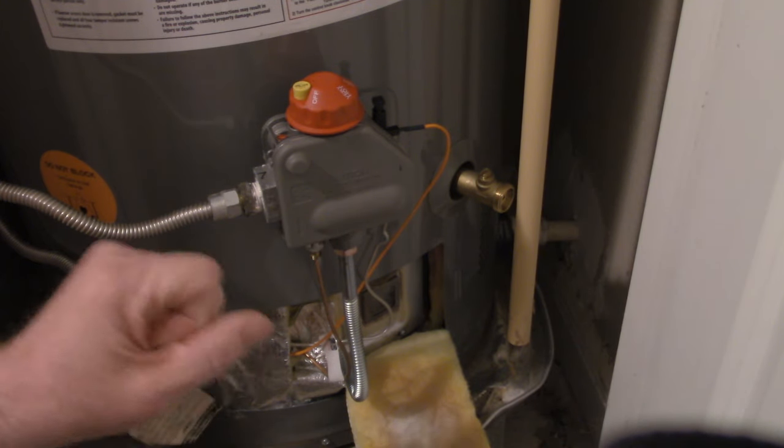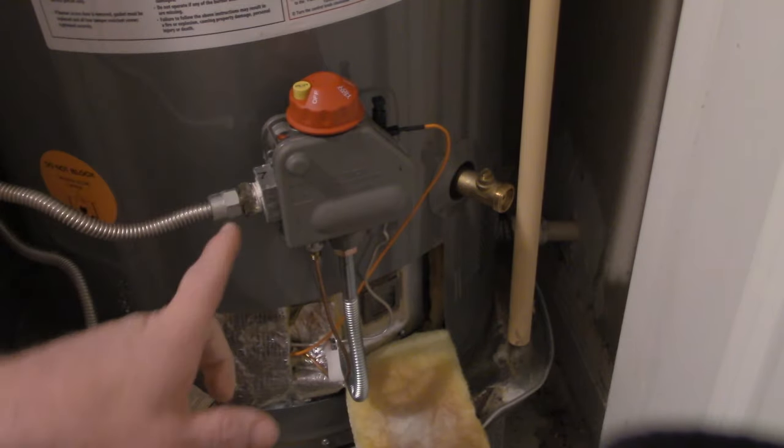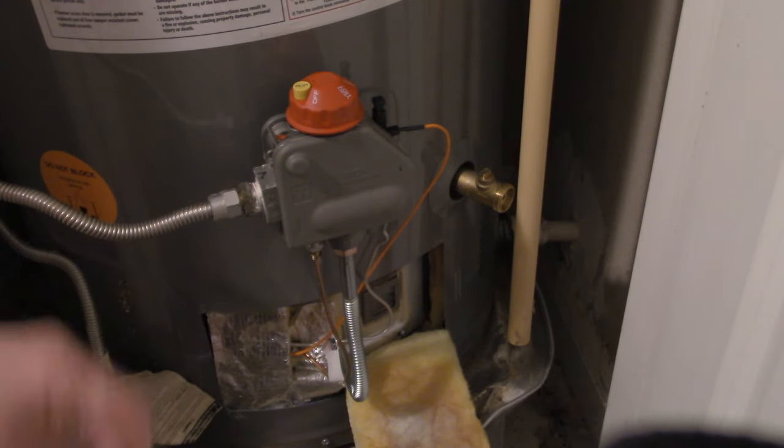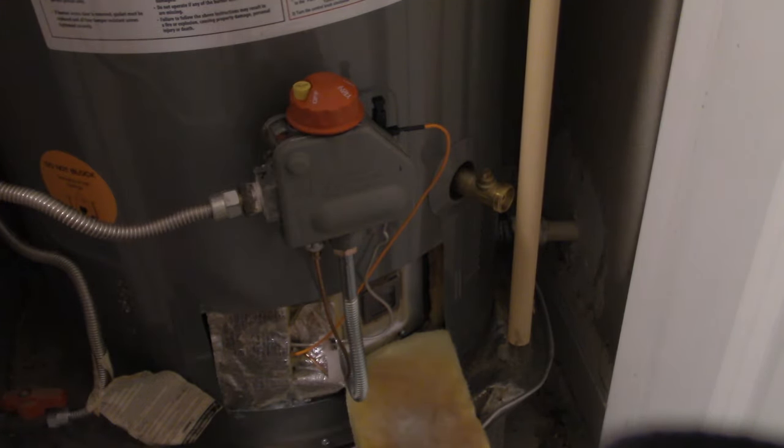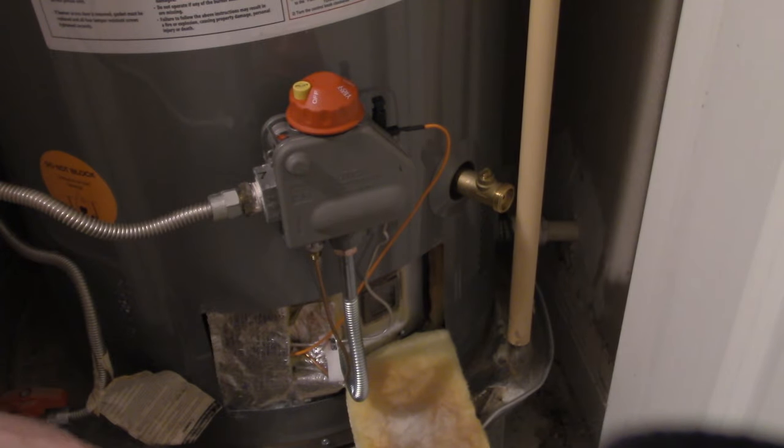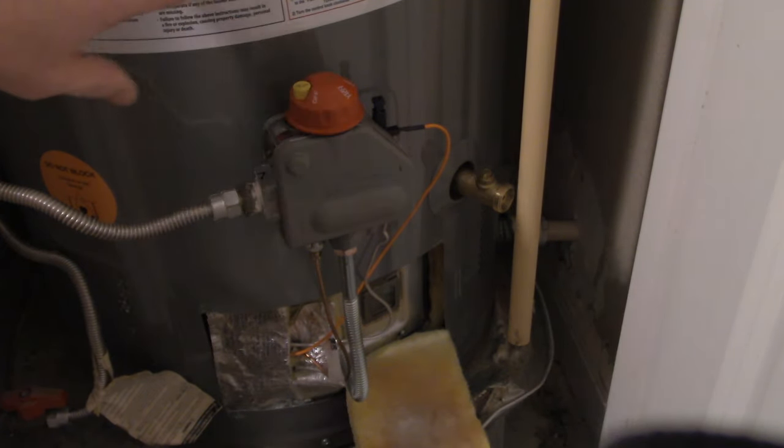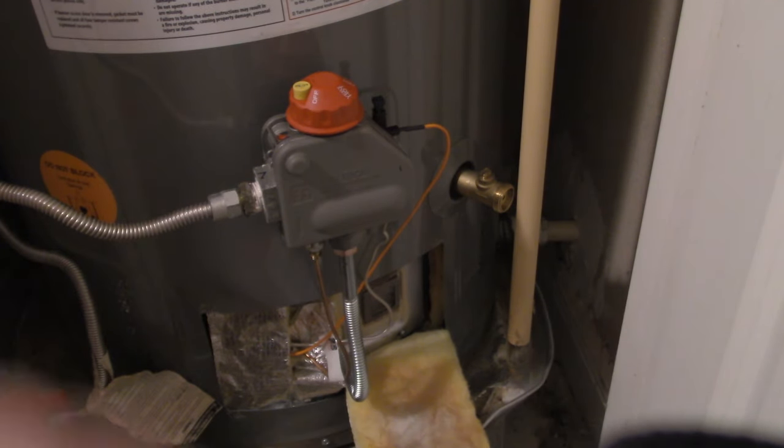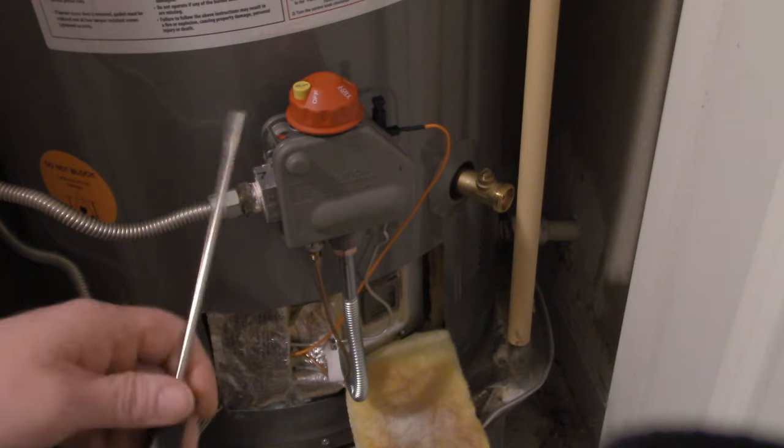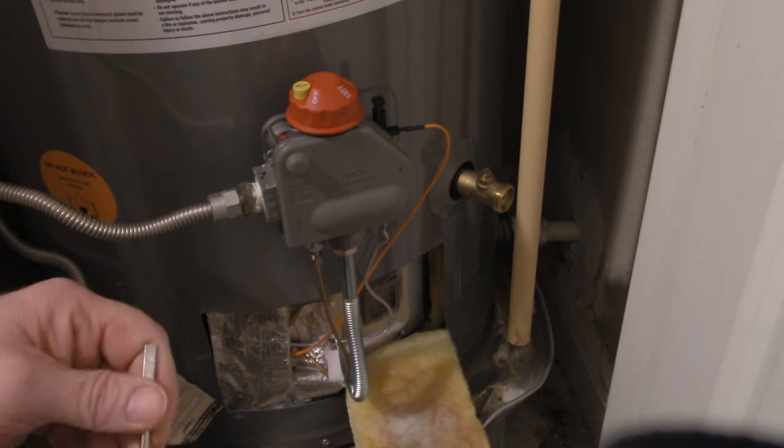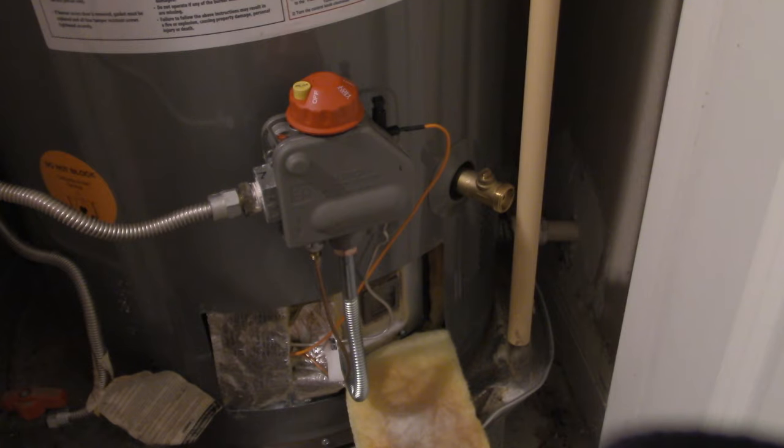So what happens is there is a sensor inside the tank, it screws in on the backside of this gas control valve, that is there to detect an over temperature condition. Again, we've all heard horror stories about these hot water heaters that over pressurize, they overheat and they end up exploding and taking off like a rocket. That is one of several safeties in there to prevent that. The problem with these is those emergency cutouts are apparently faulty.